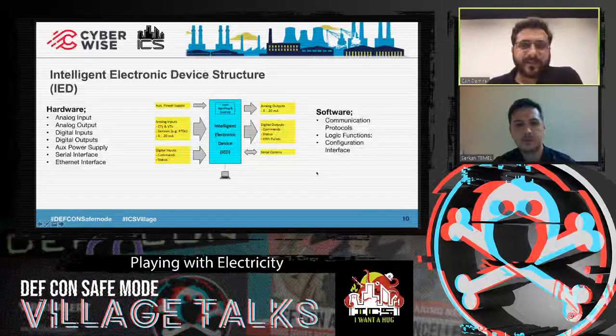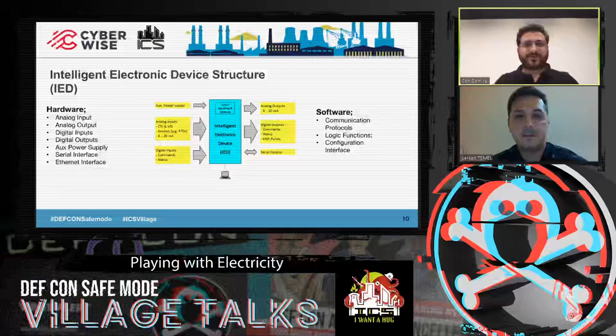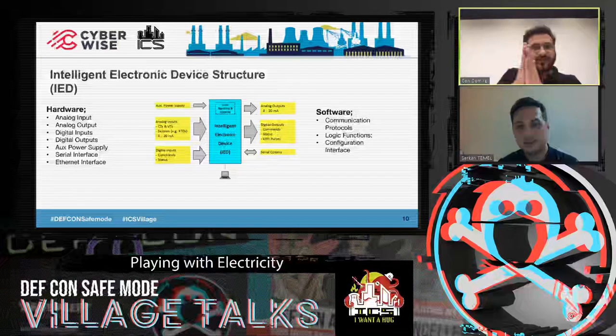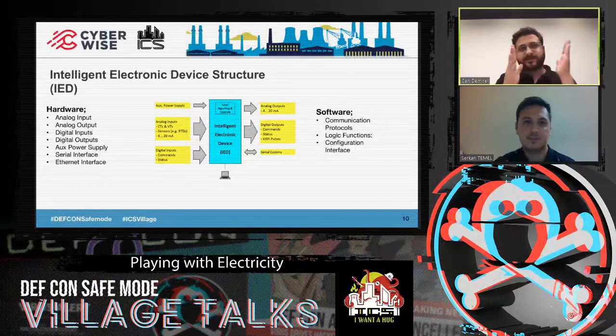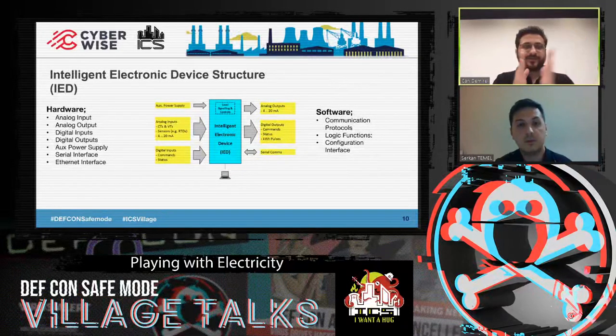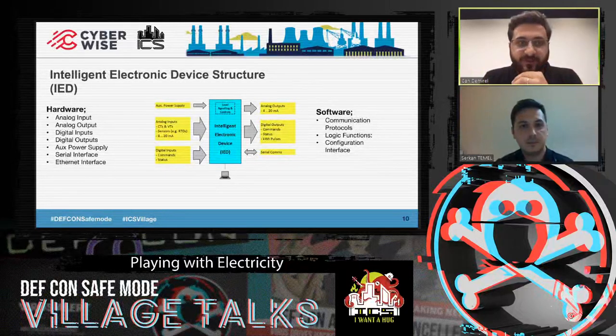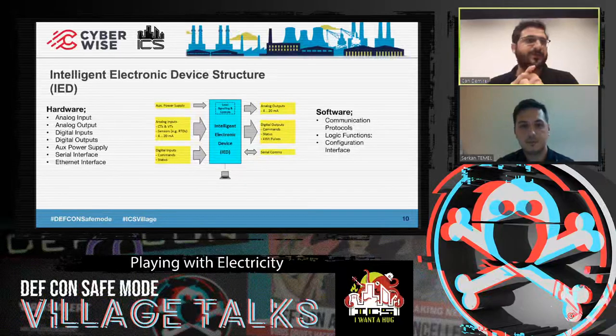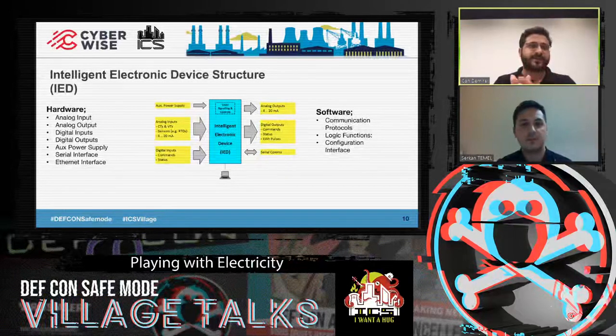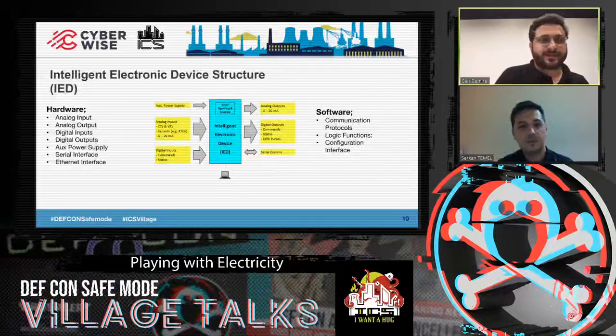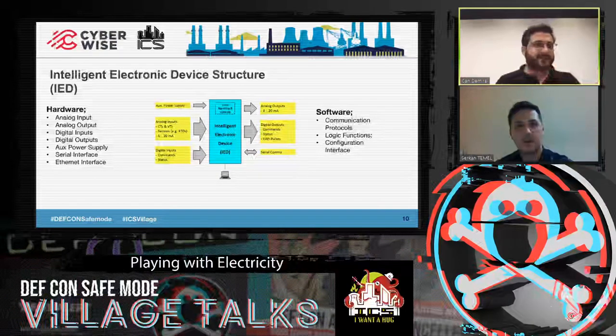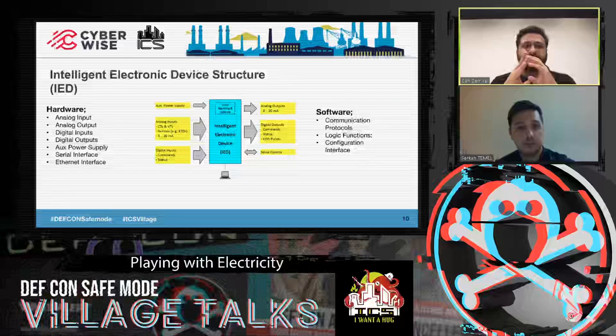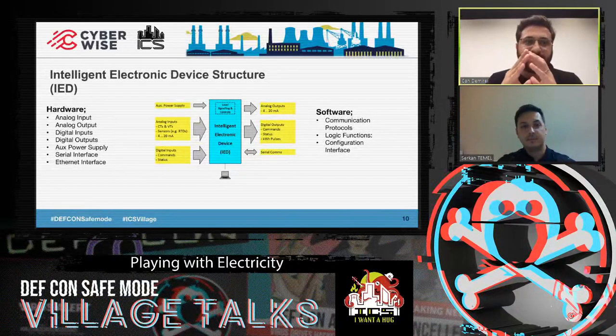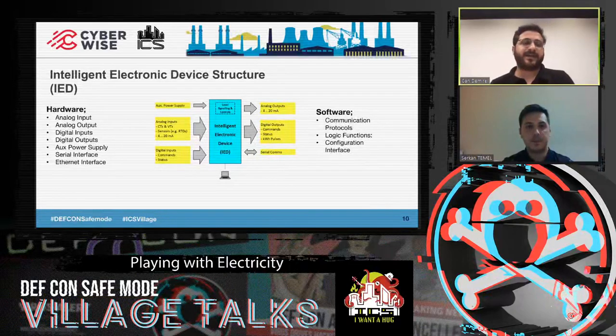Thank you, Serkan. Actually, we always get afraid or freaked out about touching such intelligent electronic devices because, as you mentioned, one part is physical and controls electricity, and one part is cyber, the RTU or SCADA applications. It's like the last line of the physical and cyber bridge. Once you control it, you control the electricity. You can control it through the RTU, or you can directly send commands to the IED, or you can trigger some SCADA application set points, and it will directly affect the intelligent electronic devices. But once you're planning a red teaming or pen testing activity, you need to be aware that such devices can affect the electricity, and you need to be really careful what you're playing with.